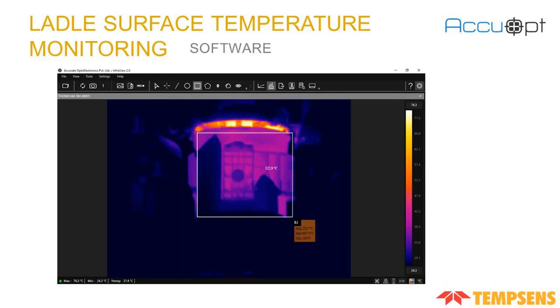This is a screenshot of our software with ladle surface monitoring. As you can see, the R1, which is the ROI drawn, has an average, maximum and minimum temperature display with an average temperature of 228.7 degrees Celsius, maximum 607.9 and minimum 100 degrees Celsius. This is the surface temperature of the ladle during the operation.